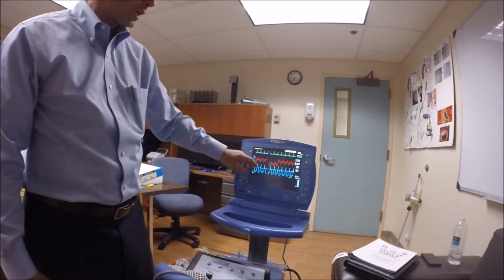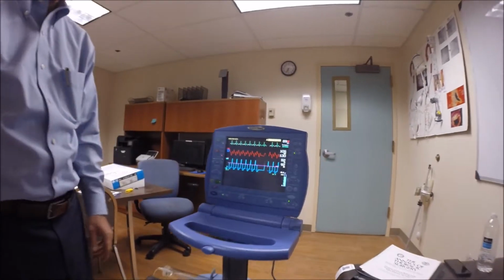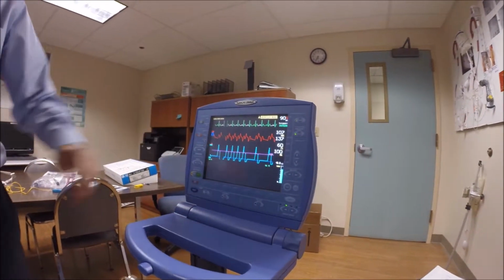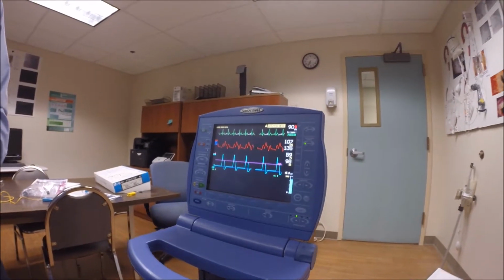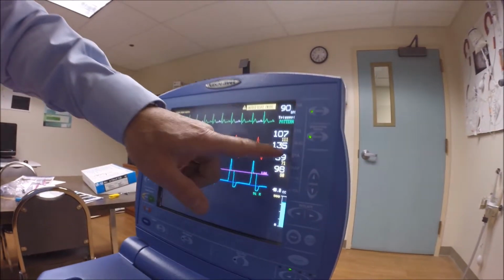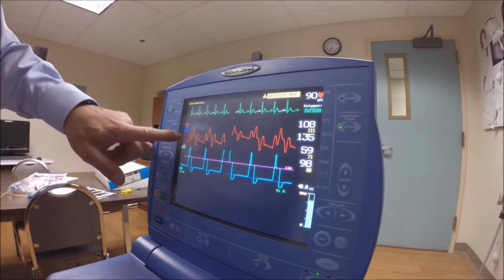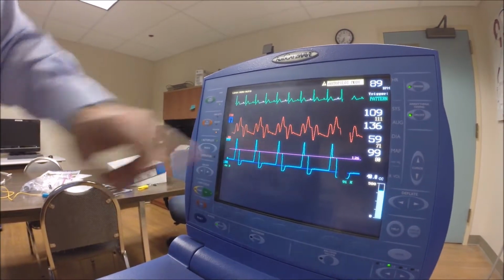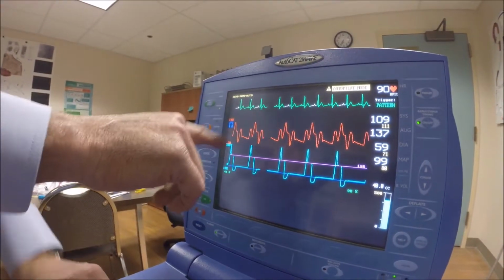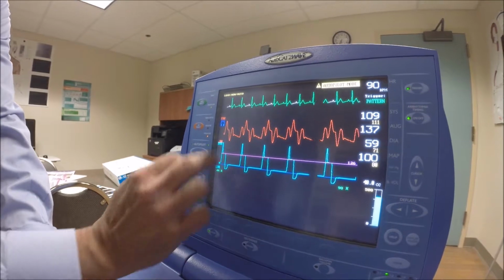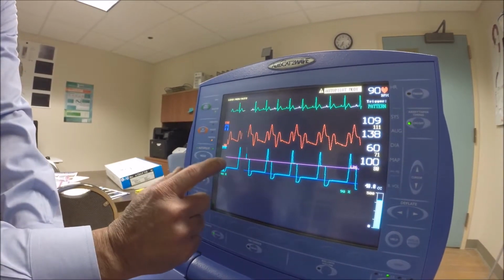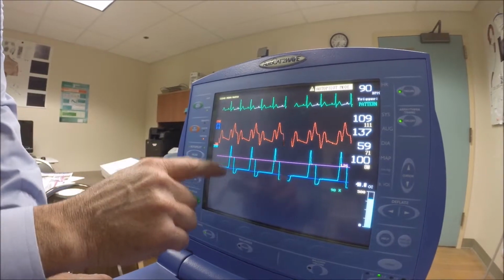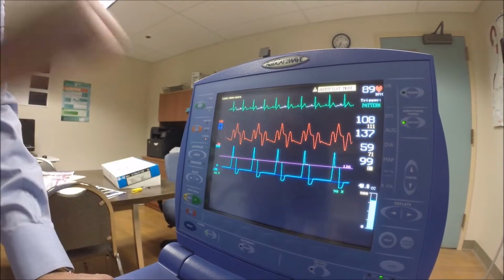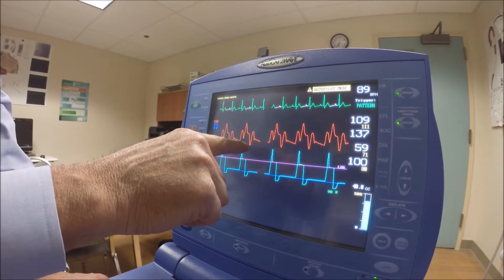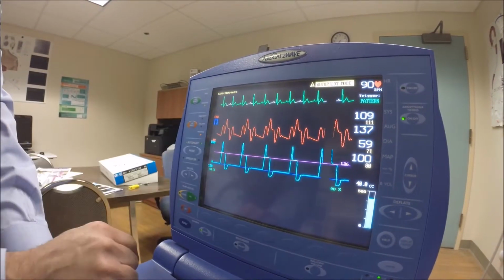Let's talk briefly about my pressures here. I'm going to go briefly to a 1-to-2 ratio, and we'll look at assisted versus unassisted pressure readings. Again, we talked about your systolic versus your diastolic, assisted versus unassisted, but on your AP waveform, right? We want to make sure that in your mountains and your valleys, your assisted systolic pressures are lower than your patient systolic, and your assisted diastolic pressures are higher than your actual patient diastolic pressures.